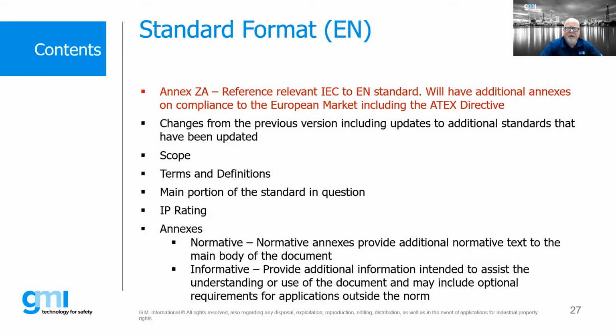So you'll see things like category and marking requirements under the ATEX directive located in Annex ZA, stating the equivalent EN standard to the IEC standard. For example, it'll say the IEC 60079-0 standard shall be EN 60079-0. That's the format you'll see on your EN standards.